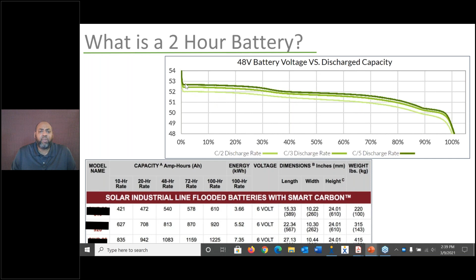Why do I bring this up? If you look at this bottom chart here, you will see for flooded lead acid batteries, if you look at their discharge rate, you will see 10-hour, 20-hour, 48-hour. So lithium batteries allow you to discharge the battery quicker. The advantage of that is that, compared to a flooded lead acid battery bank, you actually can have fewer batteries because you're getting more use out of your battery. So that is the biggest advantage of the lithium battery over the flooded lead acid battery. But again, notice that the voltage stays pretty stable throughout the duration of that discharge.